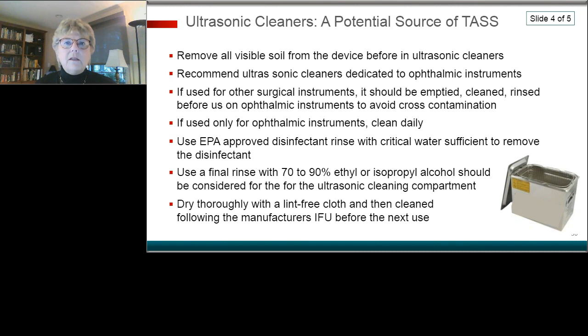By the way, if there is a problem with endotoxin, if you are ever cited to see a problem, or a patient that has an issue, another recommendation would be hydrogen peroxide on the inside before you do your final rinse and alcohol, and then rinse again. So I know that sounds excessive, but it can make a huge difference. Ultrasonic units for ophthalmic use should be dedicated.